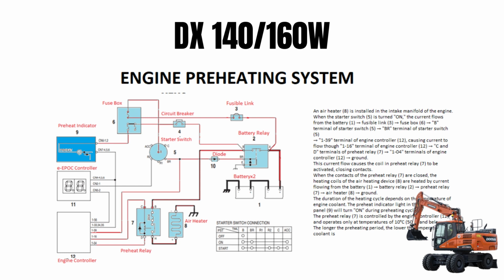This relay is energized, and now the current is here at the B point. When this relay becomes energized, this B and H have a connection. Current will pass from this, and this will go to the air heater. The air heater is already grounded. So when the contacts of the preheat relay 7 are closed, the heating coil of the air heating device 8 is heated by current flowing from the battery 1, battery relay 2, preheat relay 7, air heater 8 and ground.